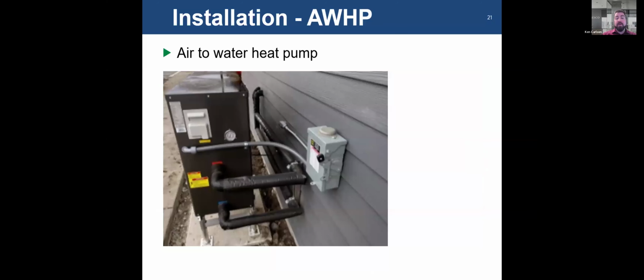The same goes for an air to water heat pump. These heat pumps are typically heavier. Probably not going to be mounted on the wall. I have seen them mounted on the wall, but special precautions were taken, and things were modified and changed structurally to support the extra weight. Typically, you'll see these on a stand. Just make sure the stand is high enough. Make sure it's on a platform strong enough to support the weight, and it's not going to shift. Concrete pad, ideally. Make sure your lines are insulated. There'll be a glycol solution in here anyway, but you don't want to lose any of that heat to the outside. You spent energy actually generating heat. You want to make sure that heat goes to the inside of the house, not outside.